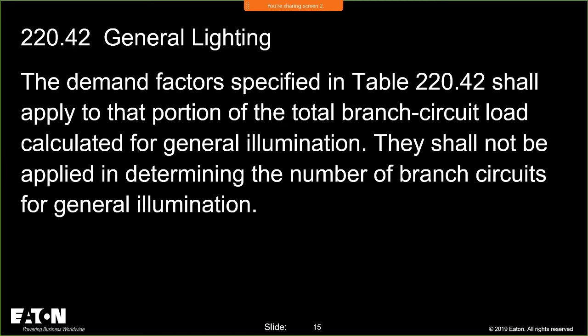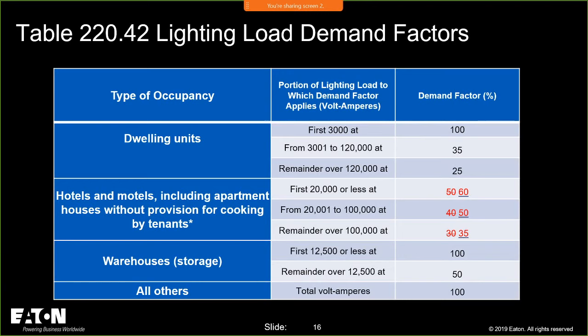But we had good justification because we had a lot of data from ASHRAE. So what we did was we modified the first for hotels, motels, including apartment houses without provision for cooking by tenants. We modified the demand factors. We moved them up from 50 to 60%, from 40 to 50%, and 30 to 35%. That sort of helped. It was almost like a governor, right? It just sort of helped us modify the load profiles, and that was really driven off of some spreadsheets and plots for these types of occupancies.